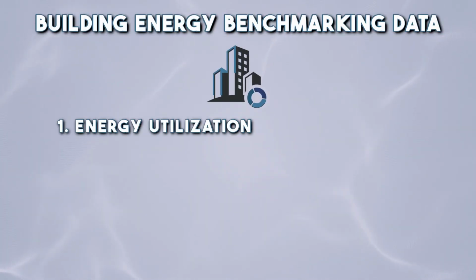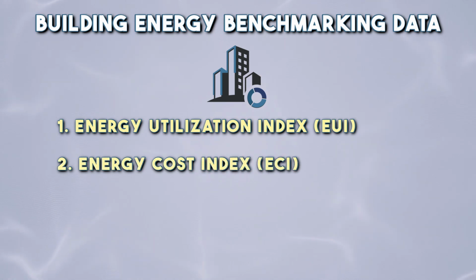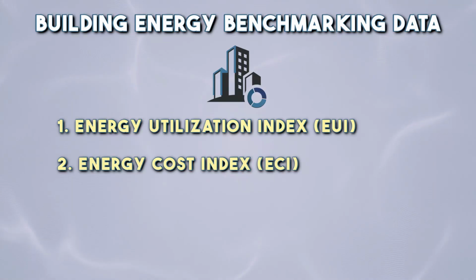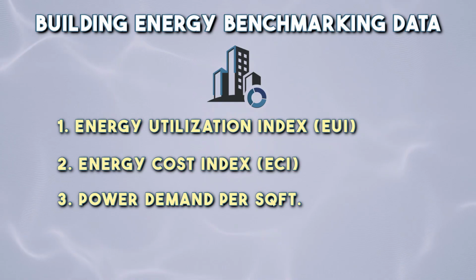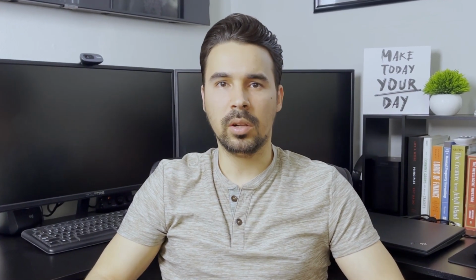Additionally, we can estimate building energy benchmarking data or performance factors such as energy utilization index and energy cost index. These are indexes that serve as a mechanism to measure the energy performance of a single building relative to other similar buildings. Even though we may need data archived for at least a year to estimate these indexes, we can still track a modified version by calculating the real-time power demand per building square foot. This energy ratio can provide real-time energy performance comparison between multiple facilities.